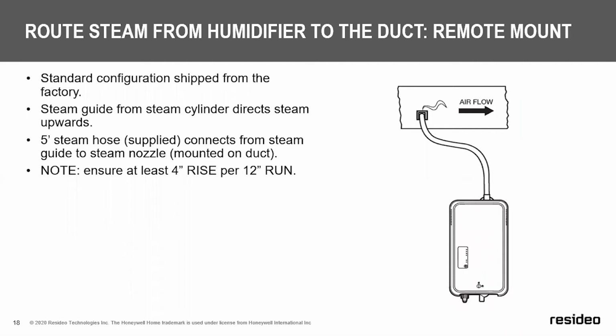For remote mounting, and in some cases this is simply mounting on the return and then using the hose to supply steam through the nozzle into the supply duct. It's the standard configuration from the factory, so it's ready to install this way. The steam guide from the cylinder directs the steam upwards. The 5 feet of steam hose which is supplied can be cut to the proper length, ensuring that you're always in a downward slope, so you do not have any way for water to accumulate, or condensation, I should say, to accumulate in the duct hose.